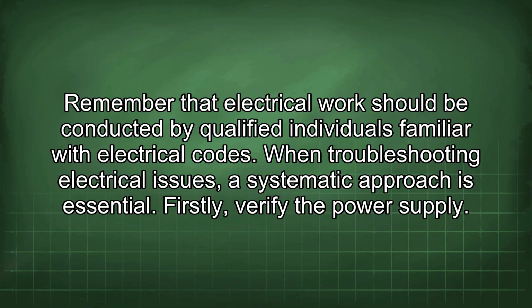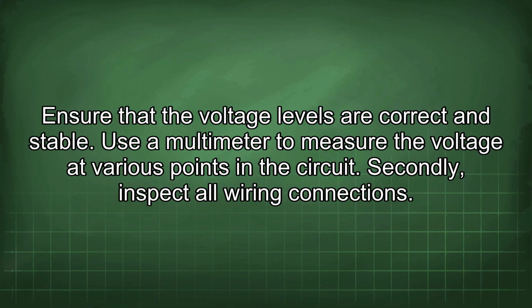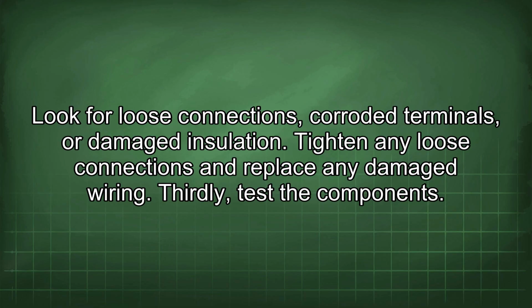When troubleshooting electrical issues, a systematic approach is essential. Firstly, verify the power supply. Ensure that the voltage levels are correct and stable. Use a multimeter to measure the voltage at various points in the circuit. Secondly, inspect all wiring connections. Look for loose connections, corroded terminals, or damaged insulation. Tighten any loose connections and replace any damaged wiring.